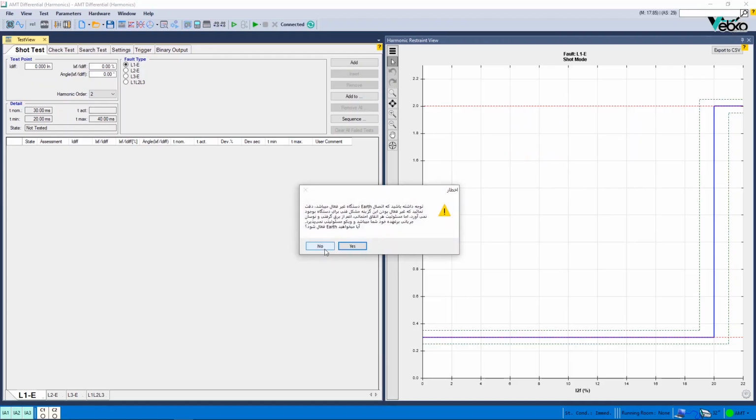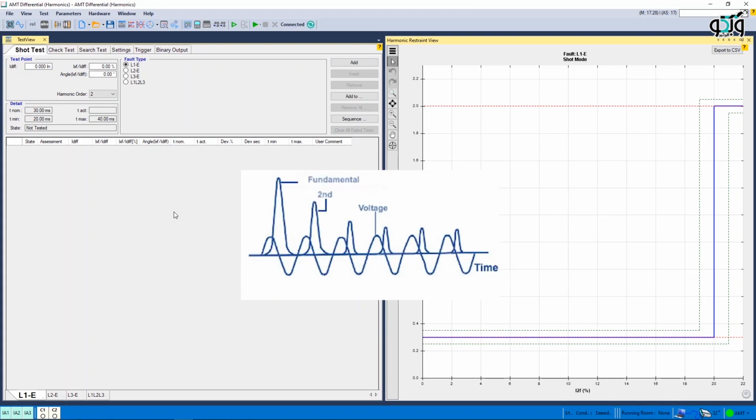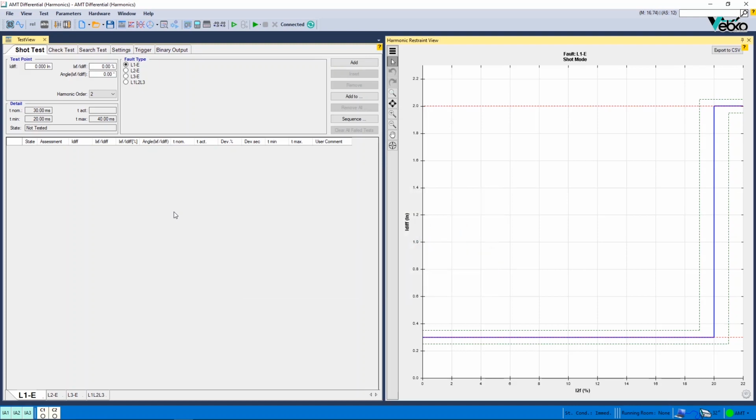At the moment of initiation, a power transformer draws a great deal of current, named inrush. If the transformer is not completely demagnetized and has some residue, it draws a great deal of inrush current, which can damage the transformer. One of the ways for detecting this inrush current at the moment of transformer initiation is to compare the secondary harmonic current with the main harmonic.